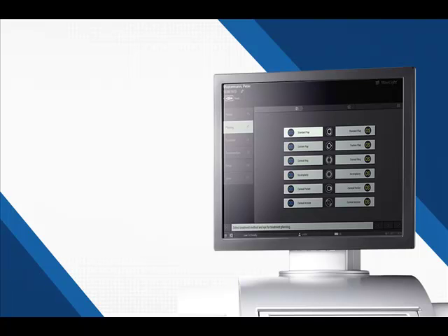So what dictates what blade to select, what blade diameter in constructing an incision, depends on the surgical technique, the parameters being used with the phaco unit, and the skill of the surgeon. As an example of sleeves, everything in a surgical suite is color-coded. This way, simply looking across the room, you can see what's on the surgical table, and you know what sizes the colors represent.